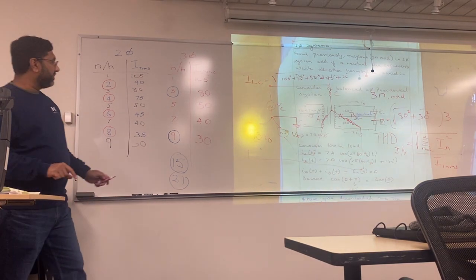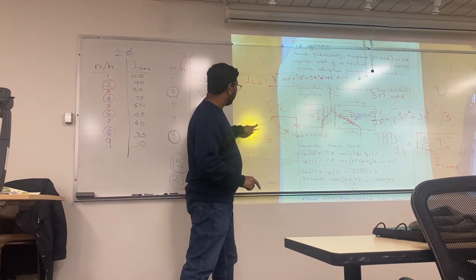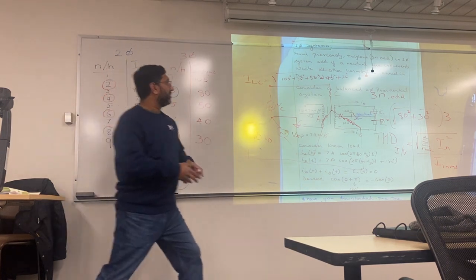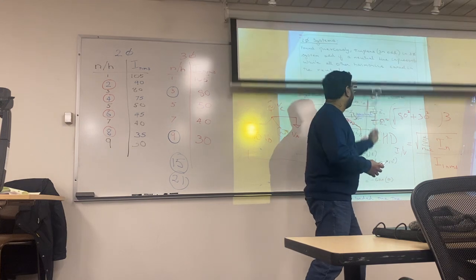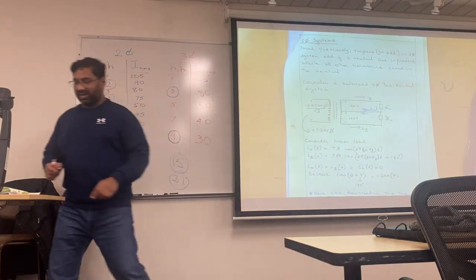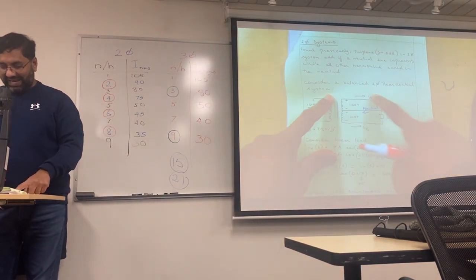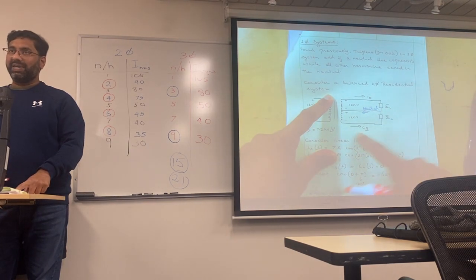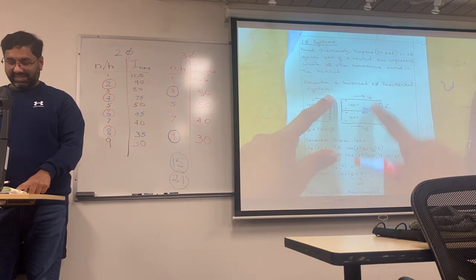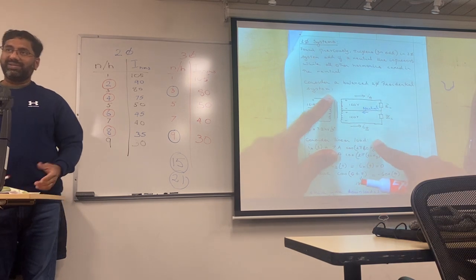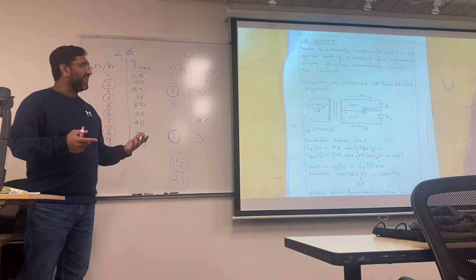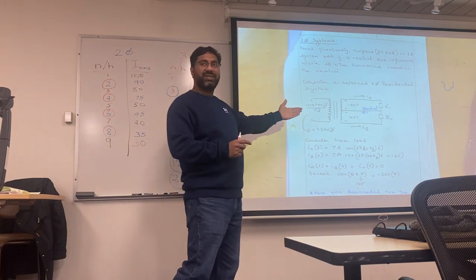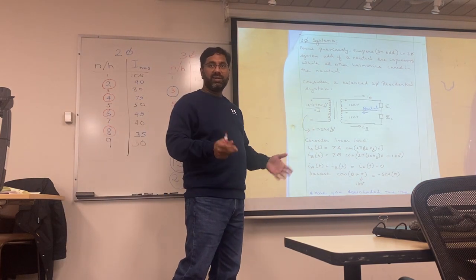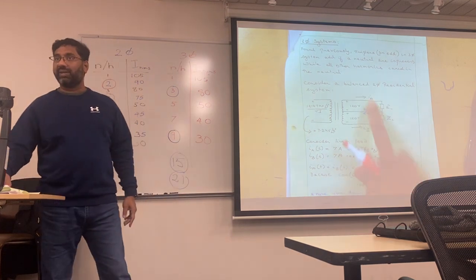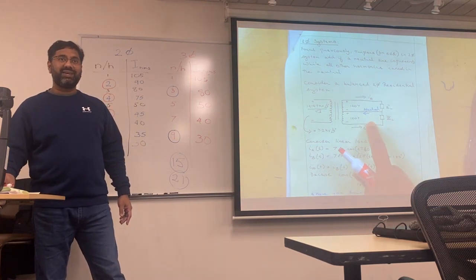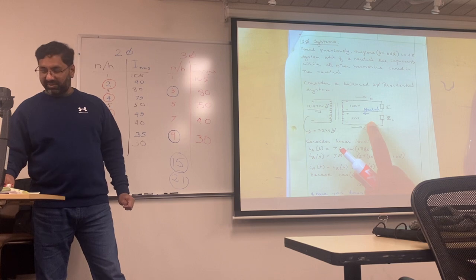So in a 3-phase, I showed you how it's 3 times because you have 3 legs, so to say. How about in a 2-phase? I mean, you have an IA flowing and an IB flowing in here, but it's only the 2nd, 4th, and 6th harmonics. So essentially, rather than doing 3 times the currents that you are concerned with, do 2 times the current because there are only 2 currents coming in. You get it? Okay, here a few yes.